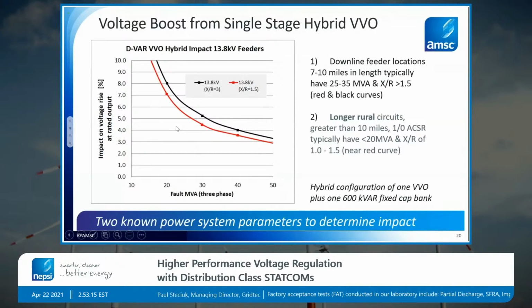Same graph, same concept, and what we call now our hybrid configuration. A very nice cost-effective way to improve the voltage impact capacity of the VVO for specifically boosting the voltage is what we call a hybrid. So we pair up the VVO, which is plus minus 1 MVAR, with a fixed 600 kVAR cap bank, and the controls automatically support that configuration, and that gives us basically another 50% of voltage impact.